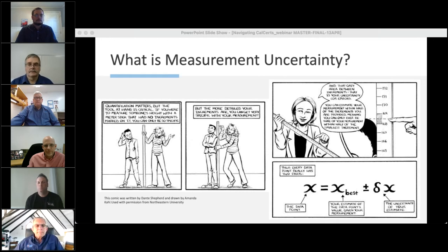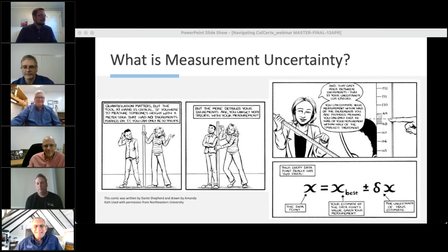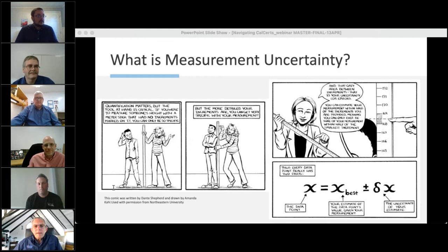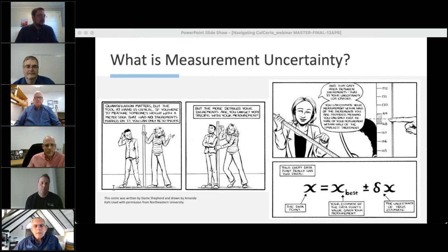Last call for audience questions. The question is: our certs include a K factor — could you elaborate on how this affects uncertainty calculations? Yes, everything is calibrated to a K factor of two, which is a 95% confidence level. Without going into extreme detail, it's basically saying 95% of the time, this is where the measurement is going to be.